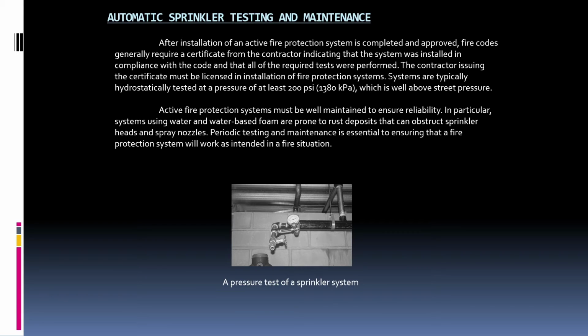Automatic sprinkler testing and maintenance. After installation of an active fire protection system is completed and approved, fire codes generally require a certificate from the contractor indicating that the system was installed in compliance with the code and that all of the required tests were performed. The contractor issuing the certificate must be licensed in installation of fire protection systems. Systems are typically hydrostatically tested at a pressure of at least 200 psi, which is well above street pressure.